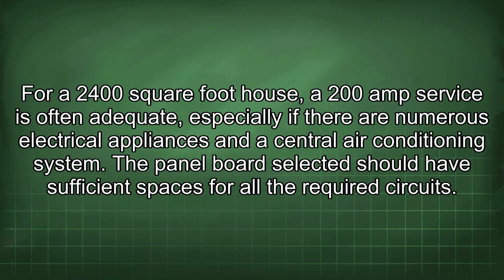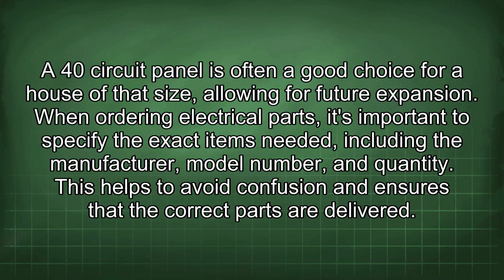For a 2400 square foot house, a 200 amp service is often adequate, especially if there are numerous electrical appliances and a central air conditioning system. The panel board selected should have sufficient spaces for all the required circuits. A 40-circuit panel is often a good choice for a house of that size, allowing for future expansion.